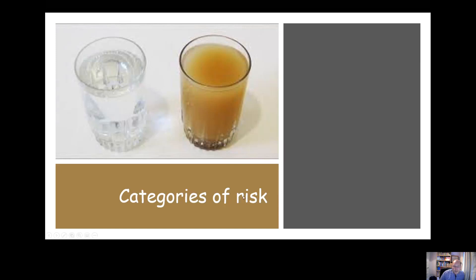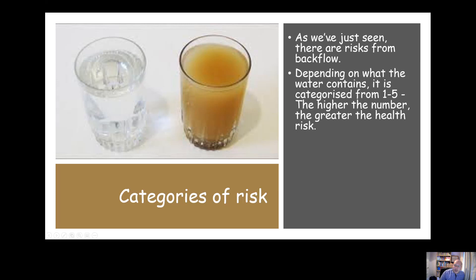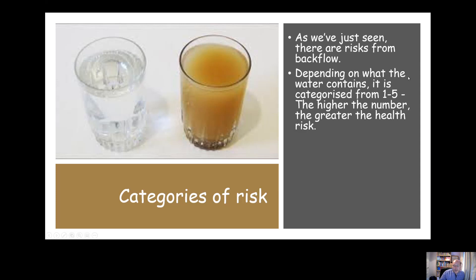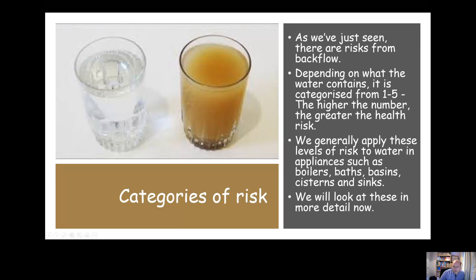We're going to look at how we can prevent that from happening, but firstly we'll look at the categories of water — the categories of risk. Depending on what the water contains, it's categorized from one to five. Essentially, one is cold, fresh, clean drinking water, while three to five represent potentially lethal water. We generally apply these levels of risk to the water in appliances — water in a boiler heating system, water in a bath, basin, or kitchen sink.